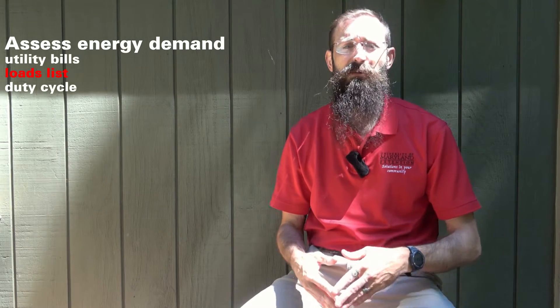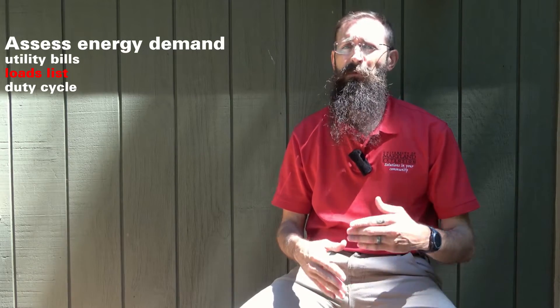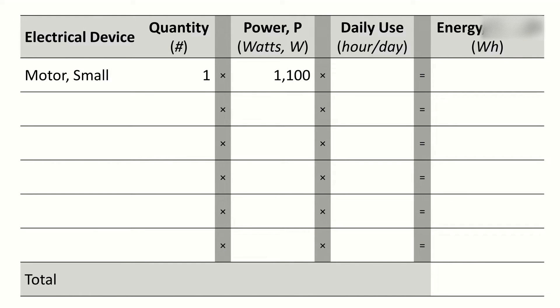For off-grid, mobile, or any battery-integrated system, an electrical loads list is a particularly useful strategy. We simply record the power rating of each device in watts as well as the number of hours we intend to operate the device. Methods for assessing power ratings include voltage and current measurements using a multimeter, referencing the manufacturer's data sheet or owner's manual, or using an electric power meter plugged into the circuit. For example, a small motor with a power rating of 1,100 watts used about 15 minutes or 0.25 hours per day yields a daily energy consumption of 275 watt hours.